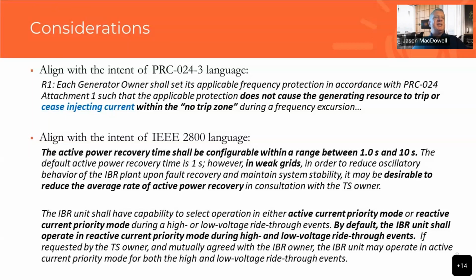Also, IEEE 2800 has some language that could be helpful for coordination. It acknowledges that the active power recovery time shall be configurable within 1 to 10 seconds, and that the active power will reduce or deviate during a fault and then recover after that fault is cleared. The language also acknowledges that in very weak grids, to reduce any oscillatory behavior or control interactions that may happen, it's desirable to reduce the average rate of power recovery. That would help eliminate, or at least reduce, the risk of those oscillations happening, and that needs to be done in consultation with the transmission system owner.